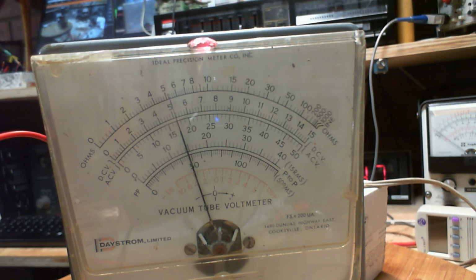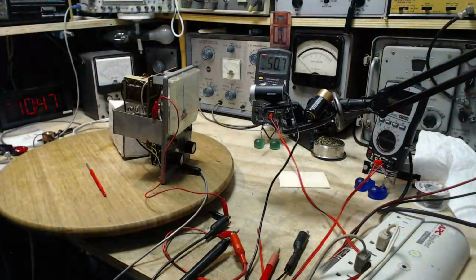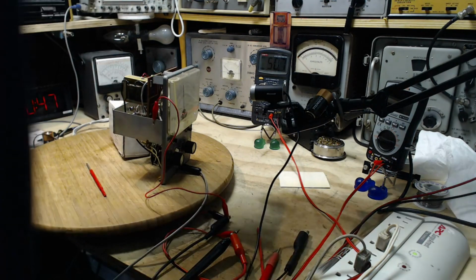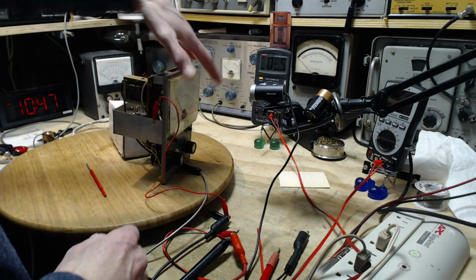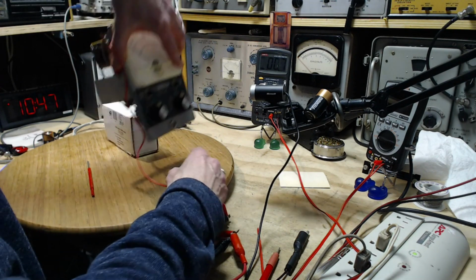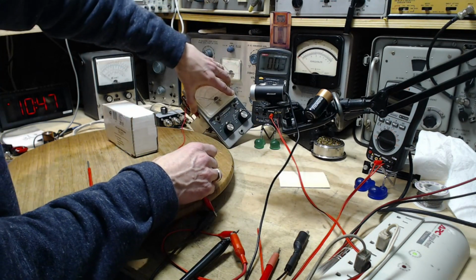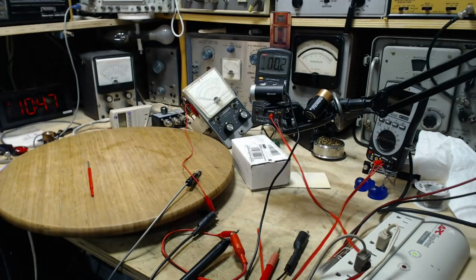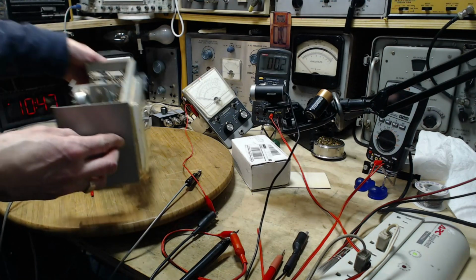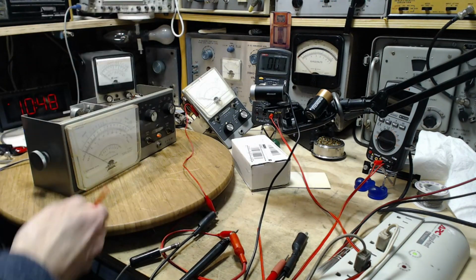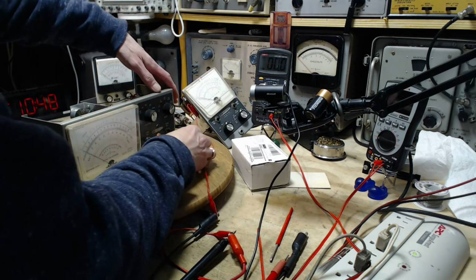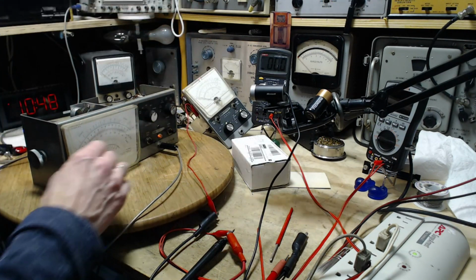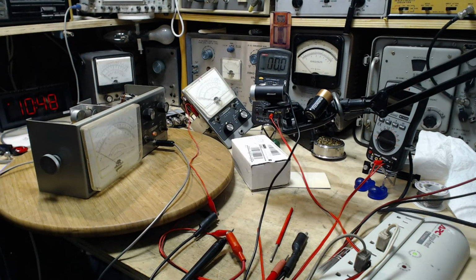Now, that other meter, I'll bring the other meter up and do the DC calibration with it. Okay, power off on the supply, so I can pull this out. Put this over here. Bring this meter back up. Oh, it's been down on the floor. It feels ice cold. Okay, we can plug this in. Set this for 150 DC plus. Put this on here, down a little bit.